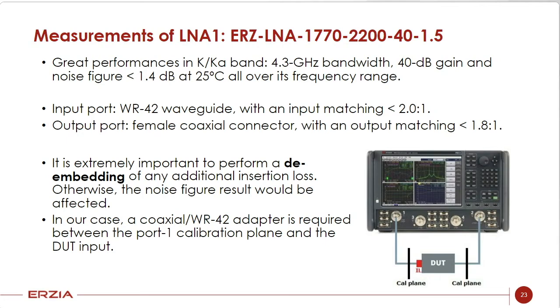It is extremely important to perform a de-embedding of extra losses you may have. So, for example, in our case, we have an adapter to change from the coaxial to the WR42 waveguide. And it is inserted between the calibration plane and our DUT. So we have to remove those losses from our result. Otherwise, the noise figure will be higher than reality.